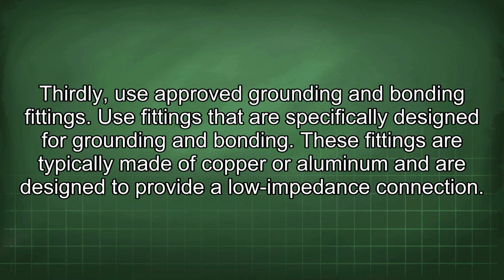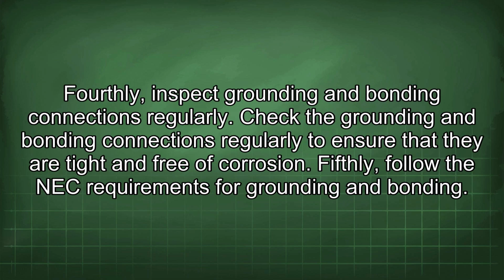Thirdly, use approved grounding and bonding fittings. Use fittings that are specifically designed for grounding and bonding. These fittings are typically made of copper or aluminum and are designed to provide a low impedance connection. Fourthly, inspect grounding and bonding connections regularly. Check the grounding and bonding connections regularly to ensure that they are tight and free of corrosion.